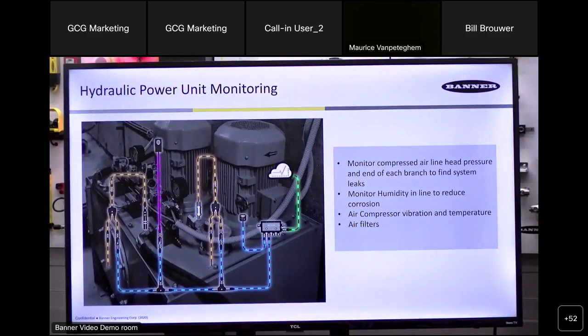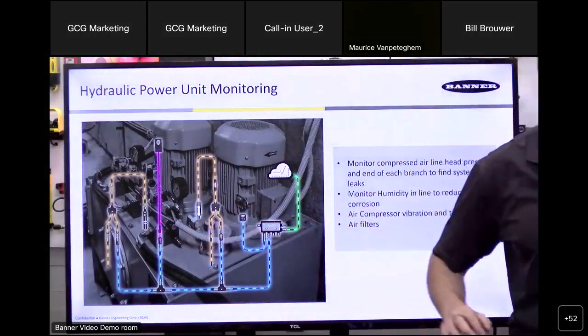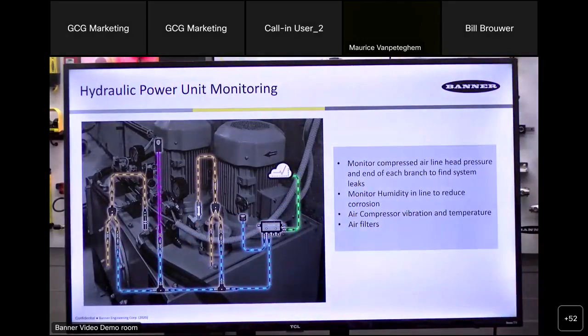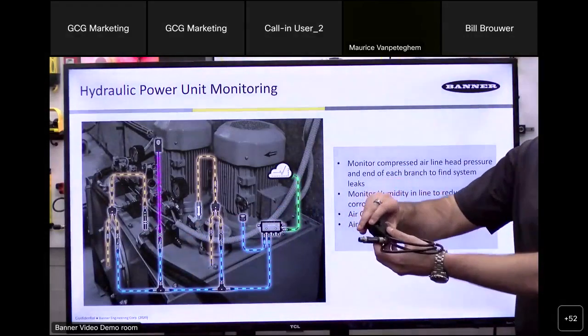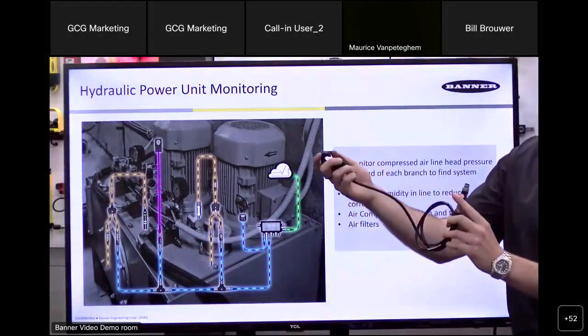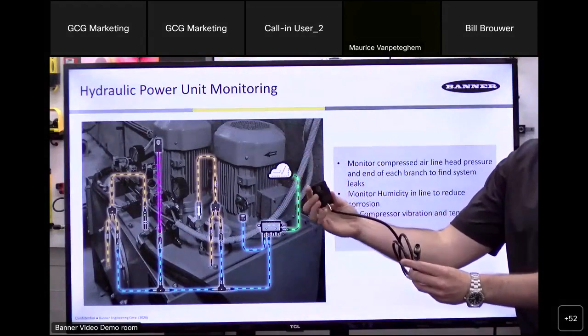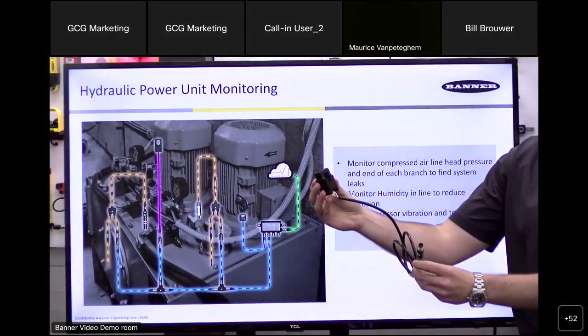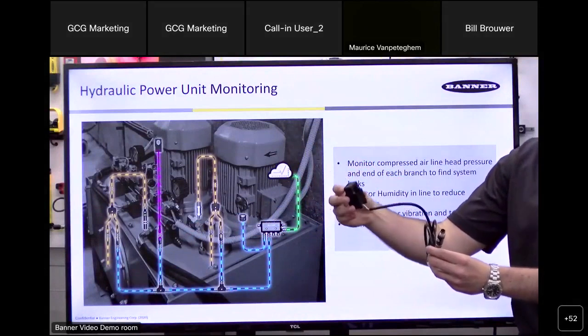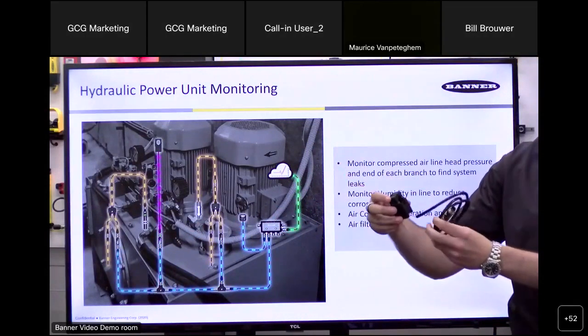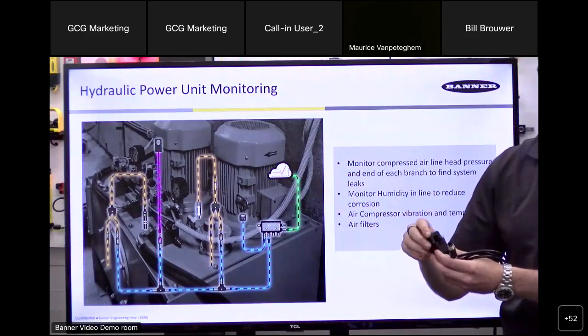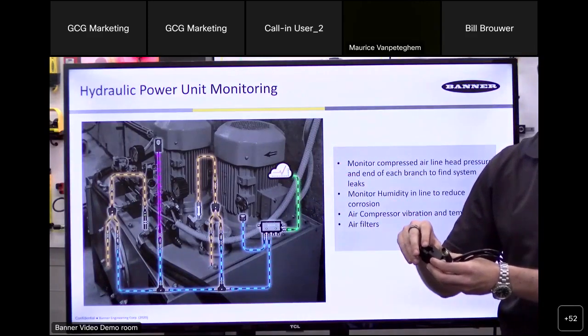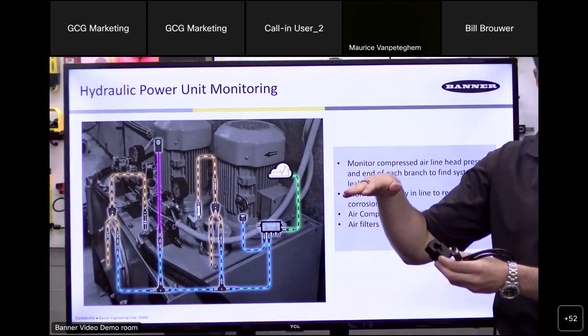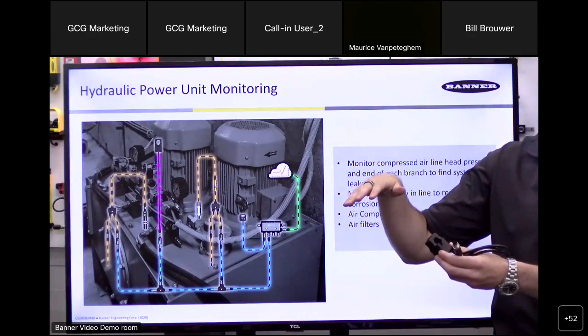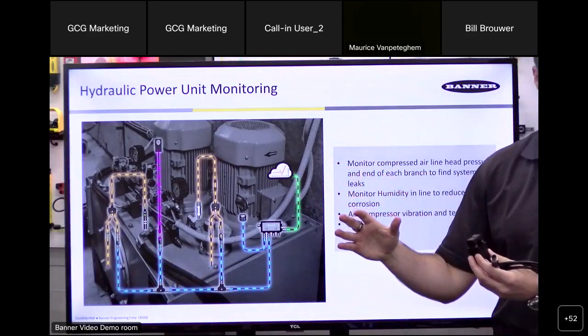Hydraulic power unit monitoring—being able to monitor the pressure and capture data from something like a CT, which we'll talk about in more detail in a bit, lets you clasp this around a wire in your motor to continuously monitor the current draw. Because if the current draw of the motor was to suddenly spike, you could set up alerts to notify personnel or technicians on the factory floor that the current draw has spiked. You should go and check on that motor, have a vibe tech check on it, to essentially serve as a check engine light for their automation equipment.